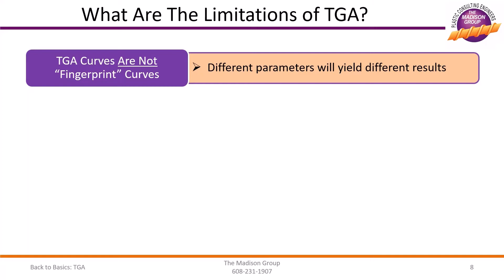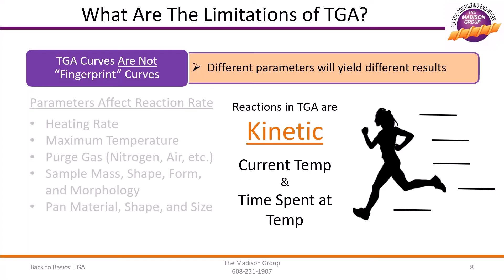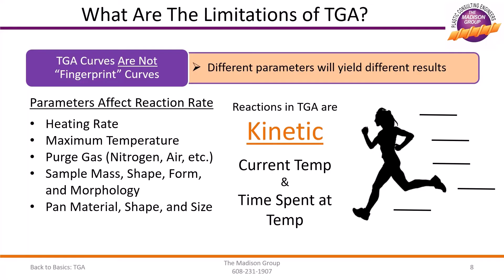While TGA is a very powerful technique to quantify the parts of a material, there are some limitations that should be addressed. Primarily, it should be understood that TGA curves are not fingerprint curves. When run with different parameters, the general shape of the curves will change because the events that occur in the TGA are kinetic in nature — highly dependent on the current temperature and the time spent at that temperature. Any parameter that changes the reaction rate will affect the general shape and temperatures at which those reactions occur. These parameters include heating rate and maximum temperature achieved, the purge gas or atmosphere of the furnace, the sample mass, shape, form, and morphology, as well as the pan material, shape, and size.